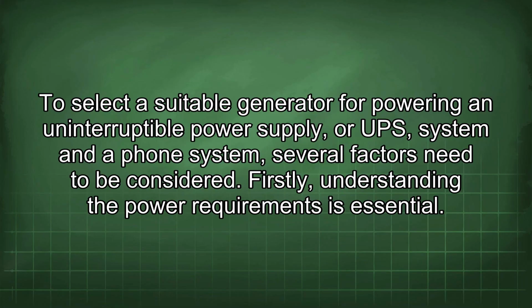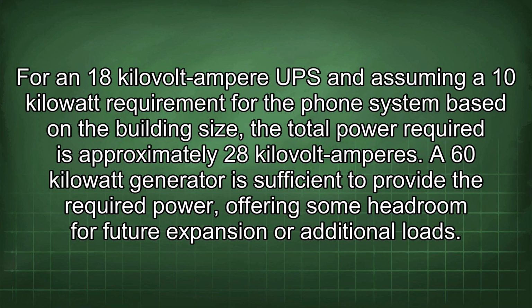To select a suitable generator for powering an uninterruptible power supply, or UPS, system and a phone system, several factors need to be considered. Firstly, understanding the power requirements is essential. For an 18 kVA UPS and assuming a 10 kW requirement for the phone system based on the building size, the total power required is approximately 28 kVA. A 60 kW generator is sufficient to provide the required power, offering some headroom for future expansion or additional loads.